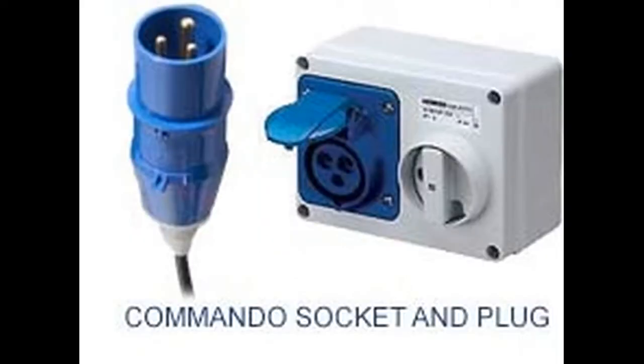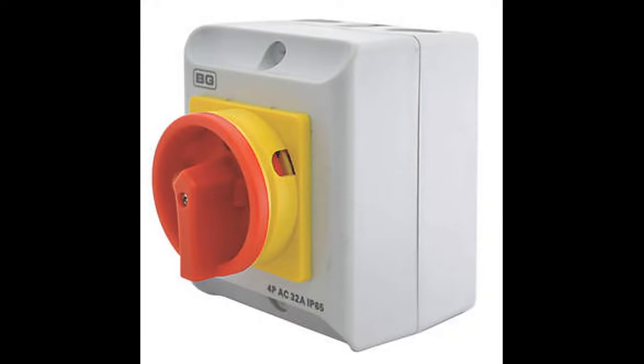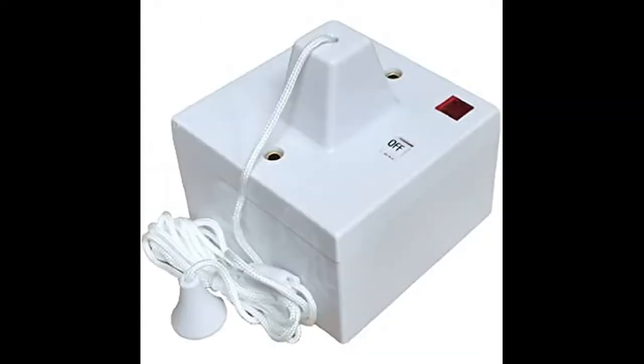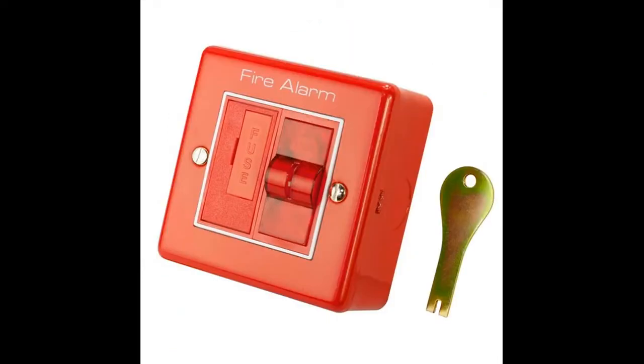So if you're using single core cables, then you need to install the cables in conduit or trunking system. And if you're using multi-core cables, like your twin and earth or your armored cable, you should provide a basket system or a tray system.